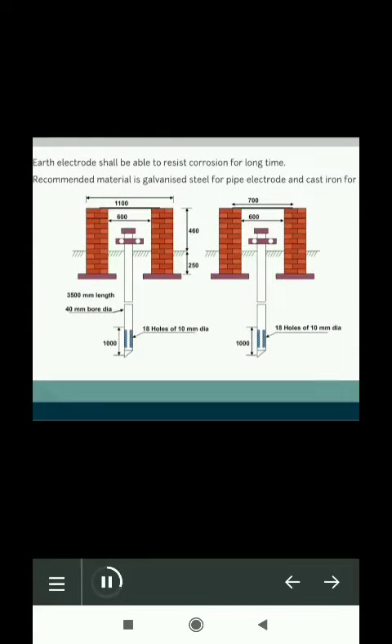Okay, but Mayank, what are the numbers for? Yes, coming to that. Firstly, this diagram shows two similar pits, that is, both of them are either equipment earthing pits or neutral pits. The important thing to observe here is that in case of similar pits, the distance between both the pits will be more than or equal to 2000 millimeters. However, in case of two dissimilar pits, that is, if one is a neutral pit and the other is an equipment pit, then the distance between both pits will be greater than or equal to 4000 millimeters.